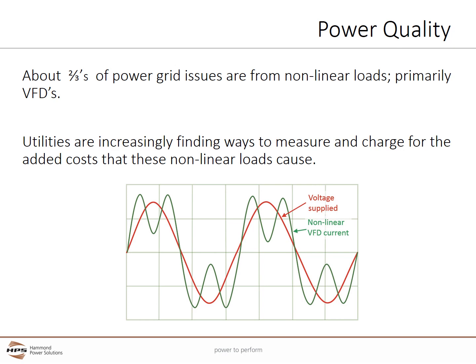Anything that rectifies AC to DC power is a nonlinear load and produces current harmonics. The line side of a VFD is basically a DC power supply, and it's a classic 3-phase nonlinear load with harmonic currents starting at the 5th harmonic, which is also 300 Hz on a 60 Hz system. Other large nonlinear loads can include heaters, arc furnaces, welders, and large DC power supplies and chargers. Overall, nonlinear loads now make up the large majority of utility loads.